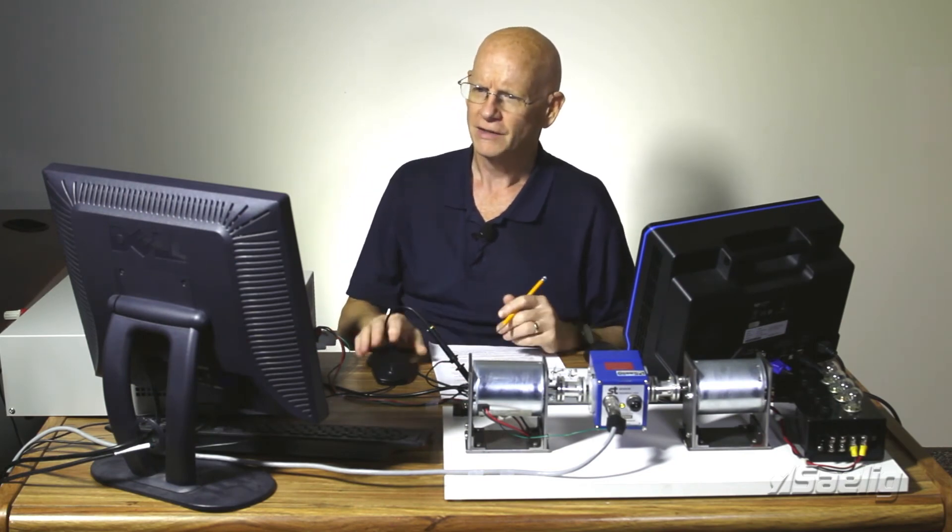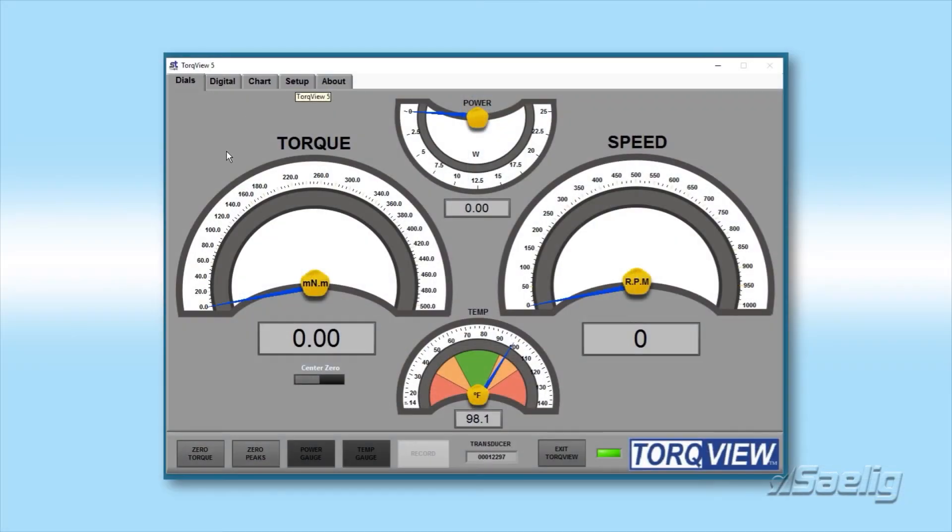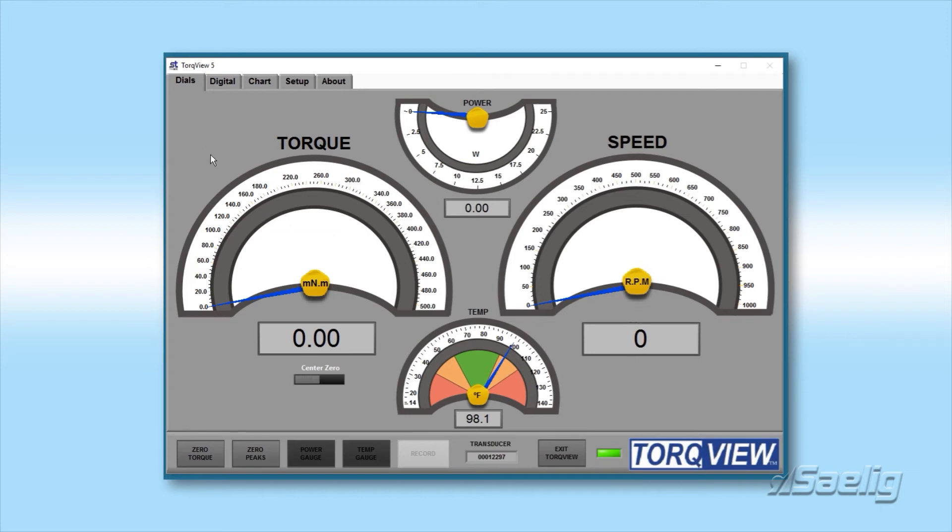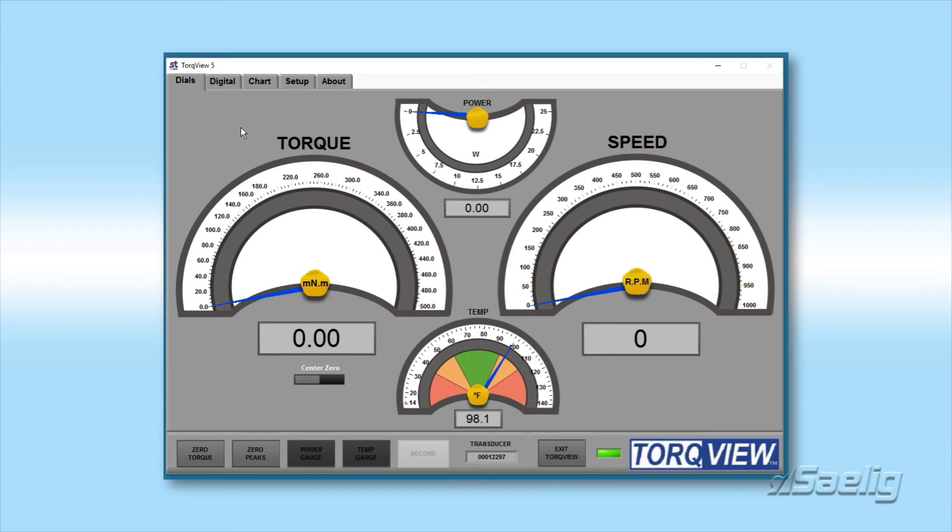So now let's take a look at TorqView 5. This is the latest one when this is all installed. You can see along the top here that there are five tabs and we have dials for torque and speed and for power. This transducer has the speed option in it, so because of that, we can get the shaft speed of the motor. We can also derive the power that the motor is producing from that. These dials are all configurable and I'll explain more about that in a minute.